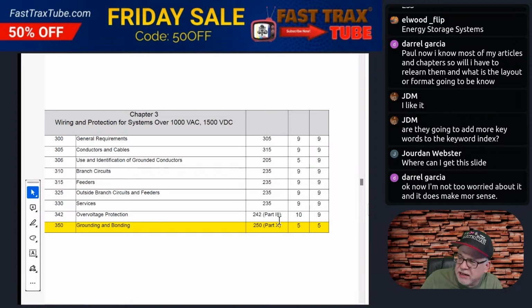So look at it right here. General requirements, these are over 1,000 volts, it's going to be 305, and now it's going to be 300 in the 2029. That's the proposed. What is 315 is going to be 305 for the conductors and cables for over 1,000 volts. Use and identification of grounded conductors in 205.